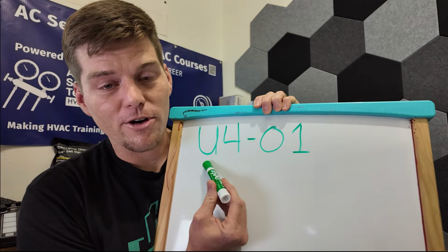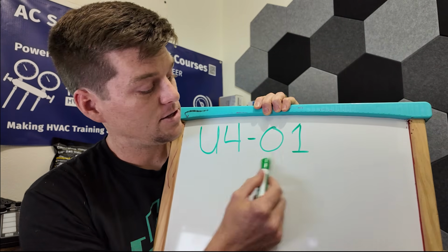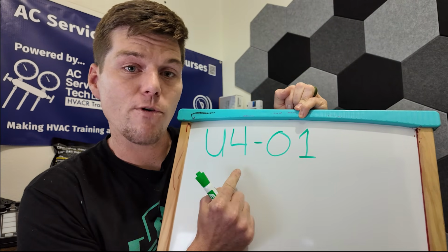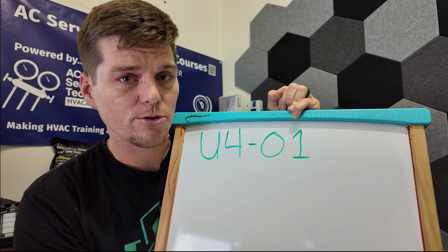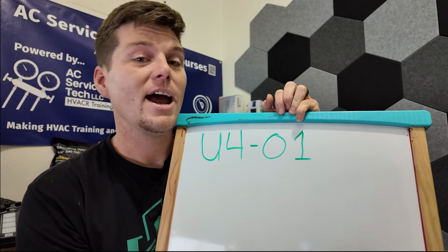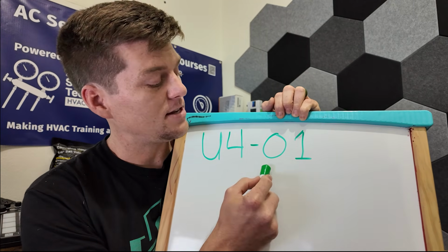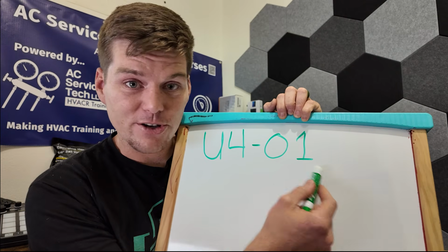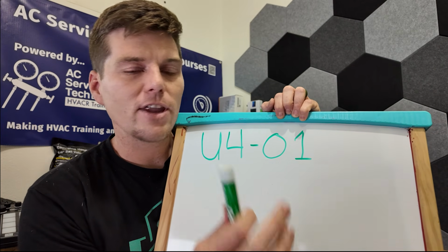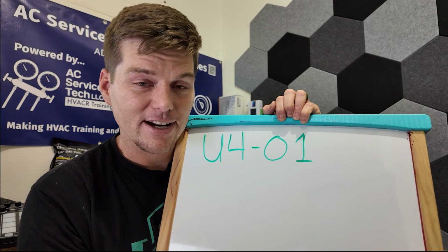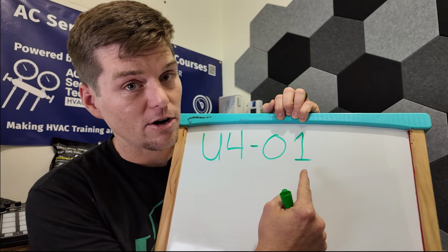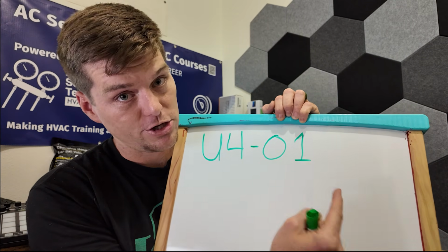You see, with a U4 error code, you have what we call a subcode. On VRV3, you won't see this part of the error code. You'll only see the U4 on the indoor unit or the outdoor unit. It wasn't until VRV4 and higher series that we got these last designations. Now, I'm not saying that the last designations here of 01 or 02 or whatever flavor they come in with the unit that you're working on is going to help you pinpoint the exact issue. I'm just showing you what the full length of the error code looks like with all 4 digits.